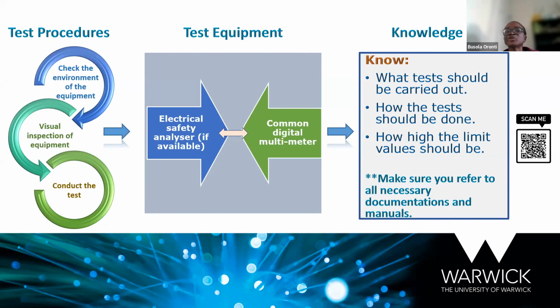If you have test equipment, fine, it makes life easier. But if not, you can use a common digital multimeter. Then you must have knowledge of what you want to test: what tests should be carried out, how the test should be done, and how high the limit values should be. You don't need to have these in your head. There's documentation. For example, I put here a QR code that you can use to download the IEC 60601. This will take you there if you focus on that QR code.